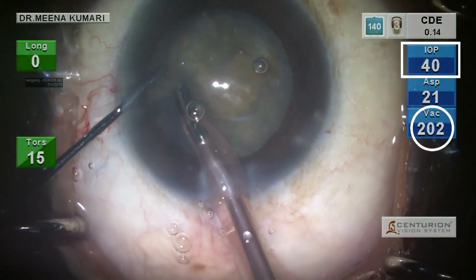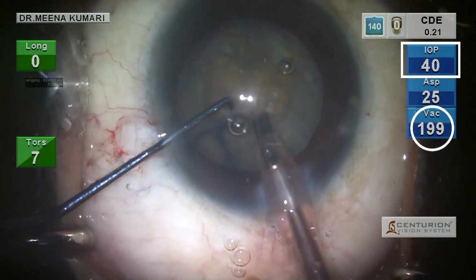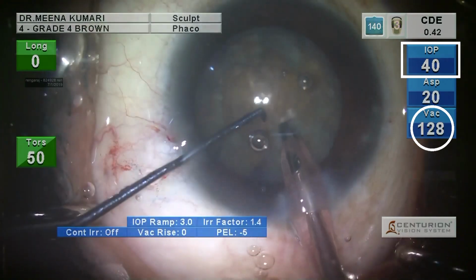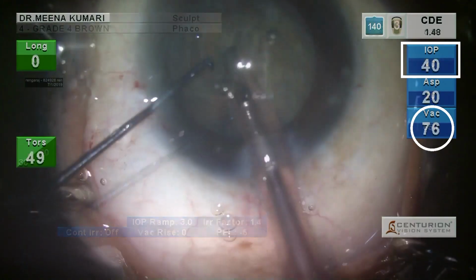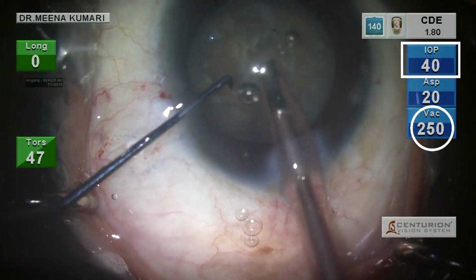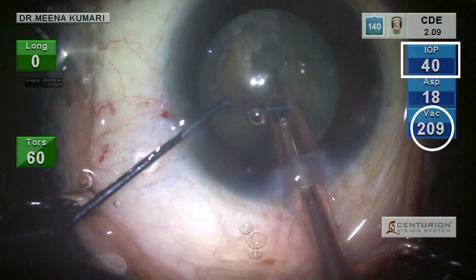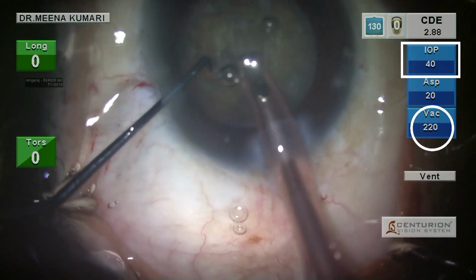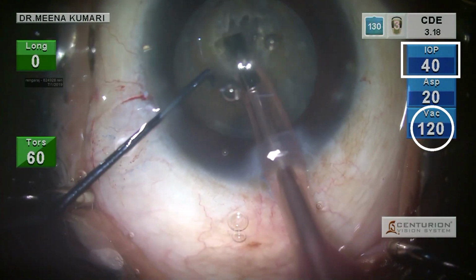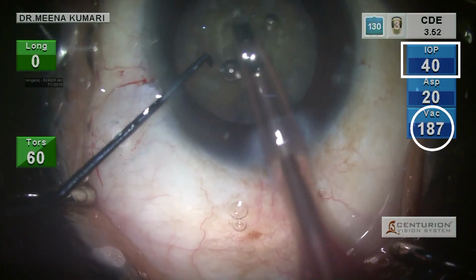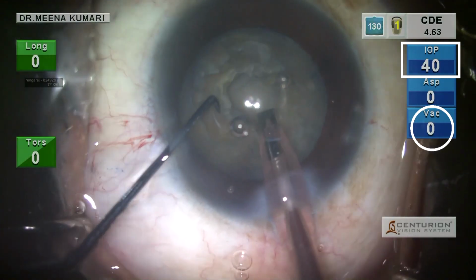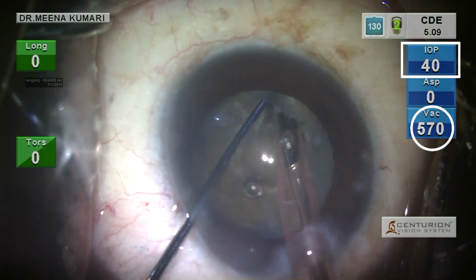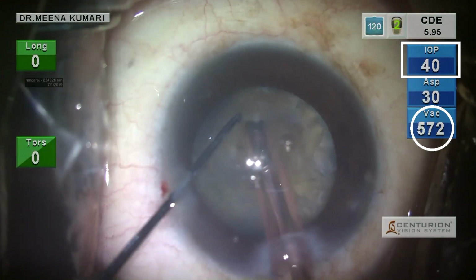The Intrepid Balanced Tip probe offers optimized energy technology. It generates a unique cutting emulsification motion that makes it glide through hard cataracts. With the balanced tip, one can reduce the torsional ultrasonic power from a previous maximum of 100% to a maximum of 80% even for black cataracts, thereby reducing the cumulative dissipated energy, which in turn reduces the damage to the endothelial cells and hastens post-op recovery.